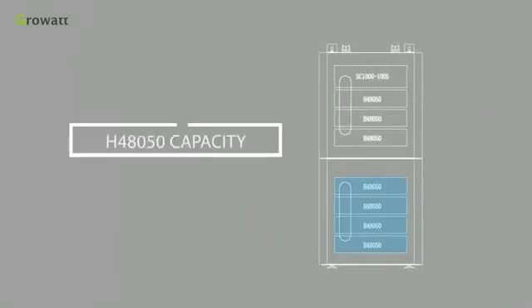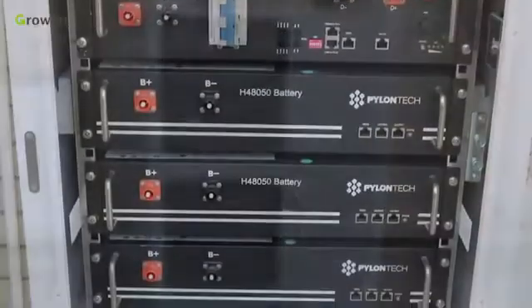There are 6 models in the SPH series. A single High Voltage Battery Cabinet can be installed with a maximum of 4 pieces of H48050 battery modules. Each battery module is 2.4 kWh, and the range of battery series connection is from 3 pieces. The battery cabinets can be stacked up, reaching a capacity range from 7.2 kWh to 24 kWh.